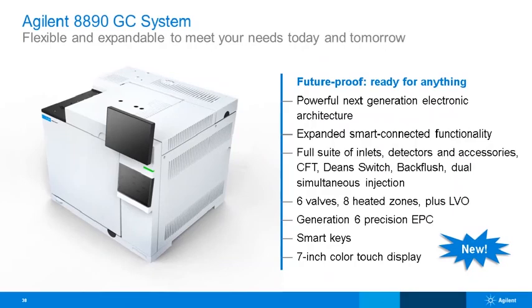And what you will notice there is a smart key. So below the touchscreen, there's an area there. And remember the smart keys from the Intuvo, where when you plug in a column, it tells the GC exactly what the column is, and what the dimensions are, what the top temperature is. Well, this is where you can buy columns now which are 8890 applicable, and you can basically have those smart keys, pull it into the GC, and the GC knows exactly what's happening.